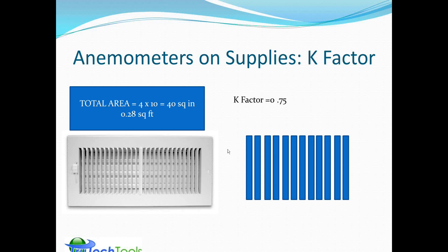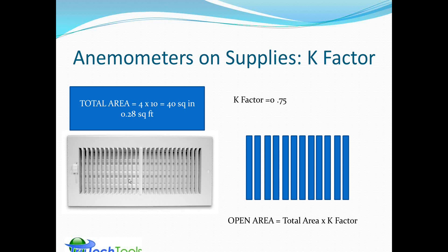If you're scanning across a grill with an air velocity meter, you'll only pick up airflow in the open areas — perhaps only 75% of the area is open. To calculate the effective open area, take the total area and multiply by the K factor. K factors can often be found in the manufacturer's data sheets for grills, and most grills run around 0.75, with some as low as 0.5 and as high as 0.80.